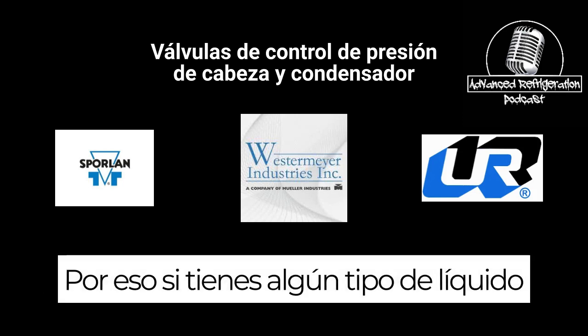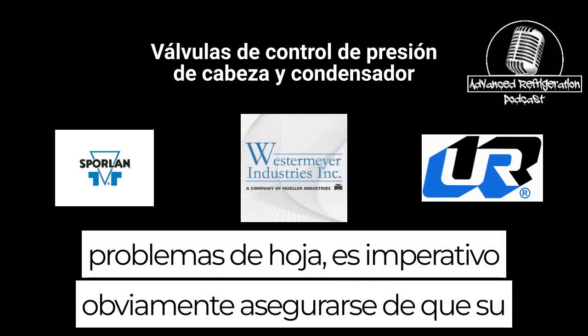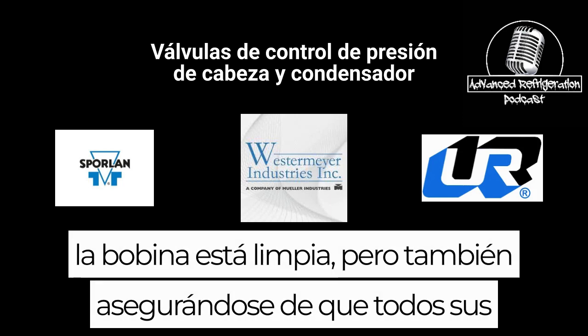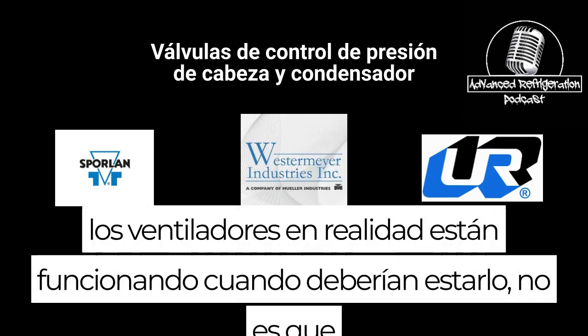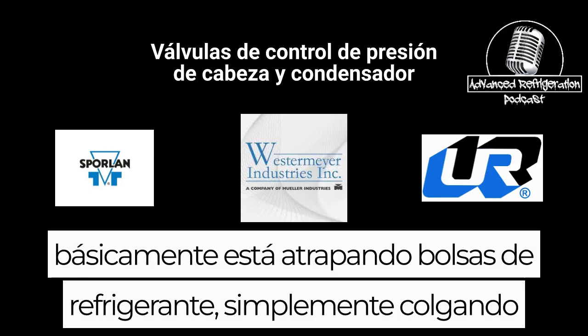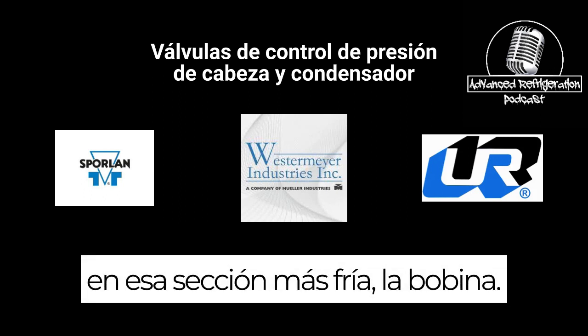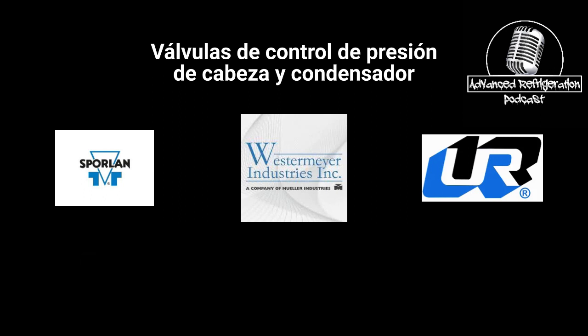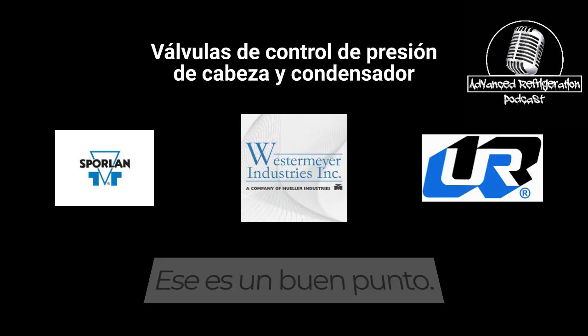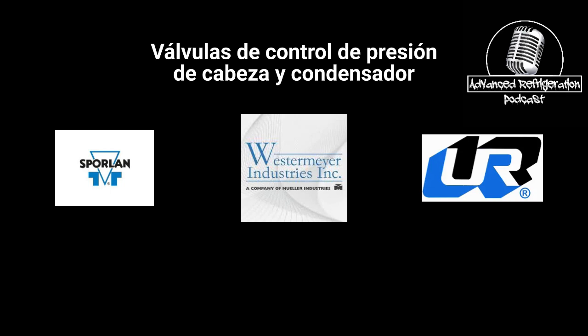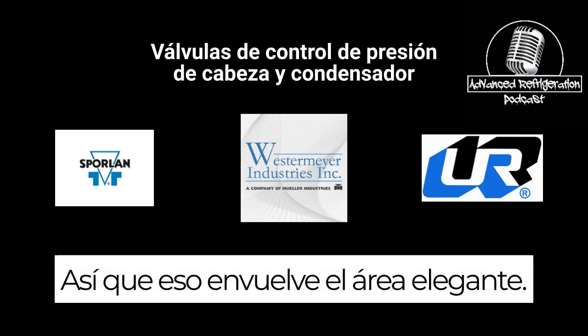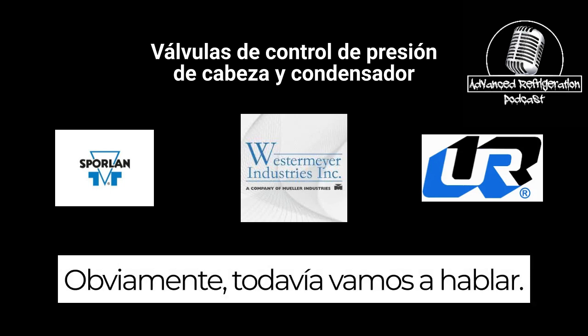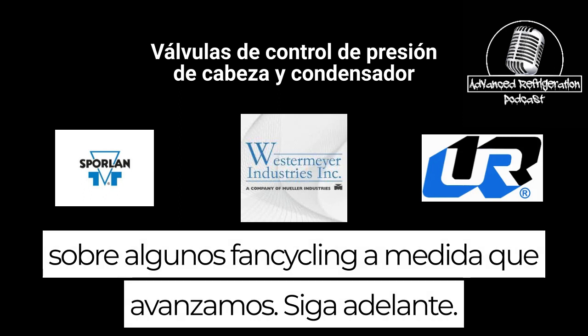That's why, if you do have any kind of liquid feed issues, it's imperative, A, obviously, to make sure that your coil is clear, but also to make sure that all your fans are actually running when they should be. Otherwise it's basically catching pockets of refrigerant and just hanging out in that one colder section of the coil. That's a good point. So that kind of wraps up the fan cycling area. Obviously, we're still going to talk about some fan cycling as we move on.